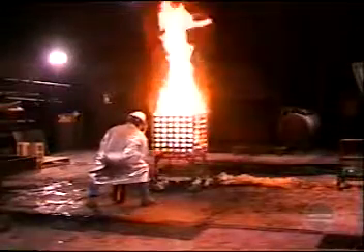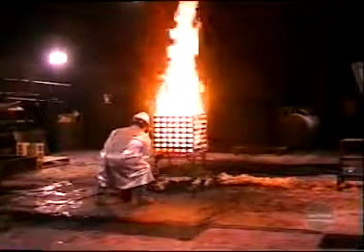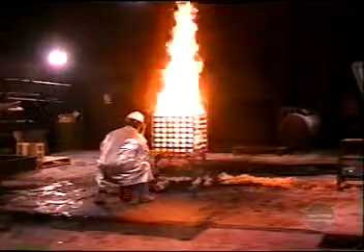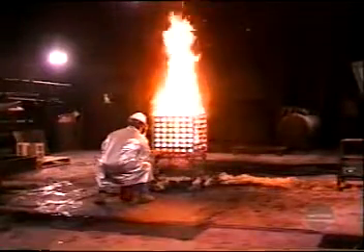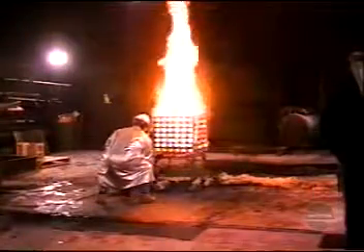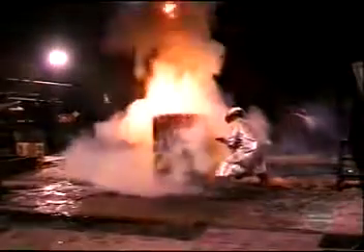This fire is a UL 2A wood crib fire conducted at UL in Northbrook, Illinois. The 2A wood crib is comprised of 78 pieces of 2 by 2 inch wood strips. The fire is started with a heptane fuel pan, and the pre-burn is typically about 6 minutes. It is repeatedly extinguished and therefore multi-UL listed with a 15.5 pound or 7 kilogram net charge weight of Halotron 1.